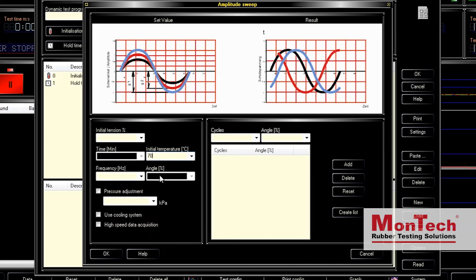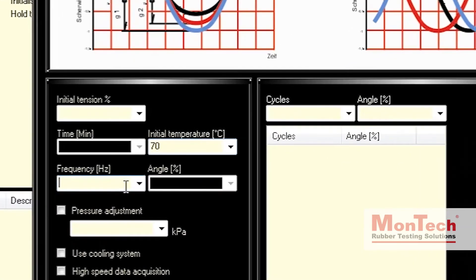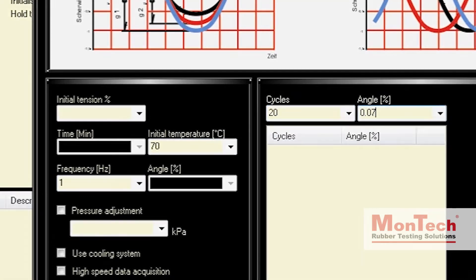During the strain sweep, the frequency of oscillation is increased to 1 Hz, with the strain amplitude increasing in steps throughout the duration of the test from 0.07% to 300% strain, well within the capabilities of Montech's DMDR3000 and DRPA3000.